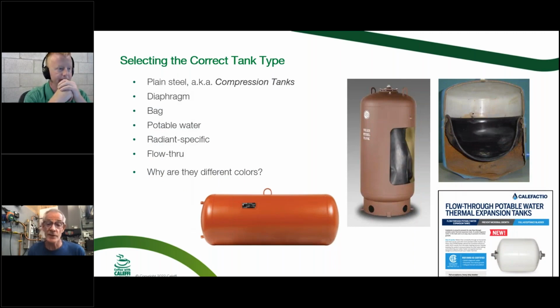So there are the tanks that are on the websites as we speak today that you can buy. There's your plain steel compression tank on the left. Now in the center, this tank is a little bit different than a diaphragm. This is sometimes called a bag or a bladder type of tank. What's different about that is you've got pretty much full acceptance, because that bladder, or that bag, whatever you want to call it, can expand to pretty much the size of the tank. If you look at the diaphragm tank on the right, they really don't want you pushing that diaphragm up against the very top of the tank.